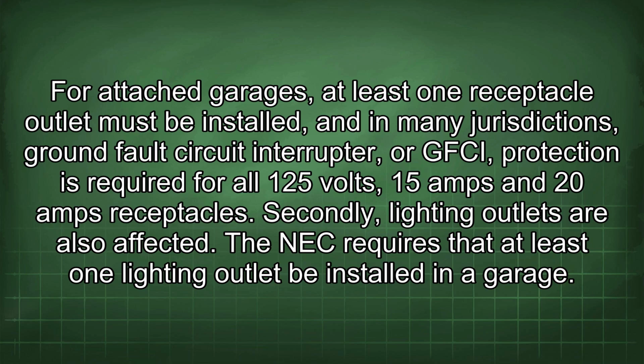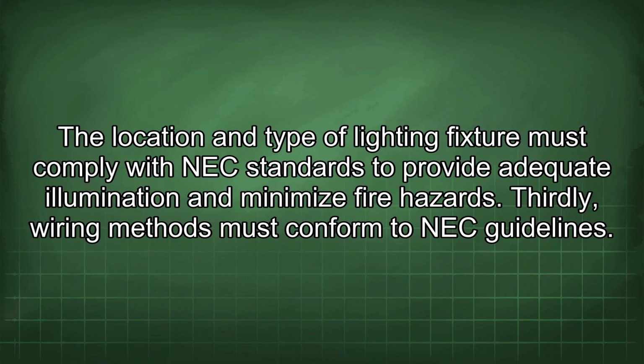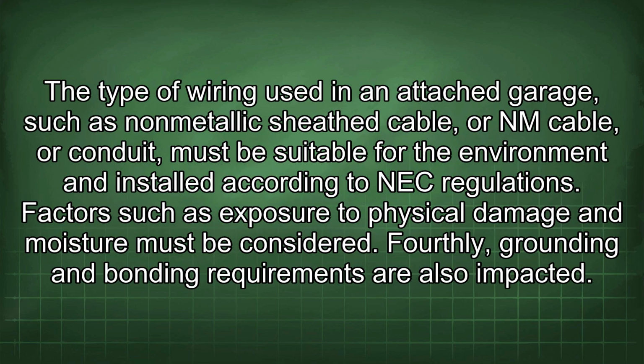Secondly, lighting outlets are also affected. The NEC requires that at least one lighting outlet be installed in a garage. The location and type of lighting fixture must comply with NEC standards to provide adequate illumination and minimize fire hazards. Thirdly, wiring methods must conform to NEC guidelines. The type of wiring used in an attached garage, such as non-metallic sheathed cable, NM cable, or conduit, must be suitable for the environment and installed according to NEC regulations. Factors such as exposure to physical damage and moisture must be considered.